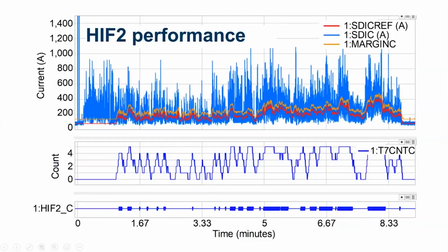The relay compares this counter value with a threshold inside the relay to assert these bits. As soon as the counter is high, this bit asserts. When the counter starts reducing past a certain value, the bit starts dropping out. This is how the relay asserts this tripping bit for a specific fault. In this case, the SDI deviation wasn't sufficient for the bit to be constantly asserted. That's why you see this chattering bit. All these settings, like how much the counter should increment and the thresholds the counter is compared with, are calibration settings.